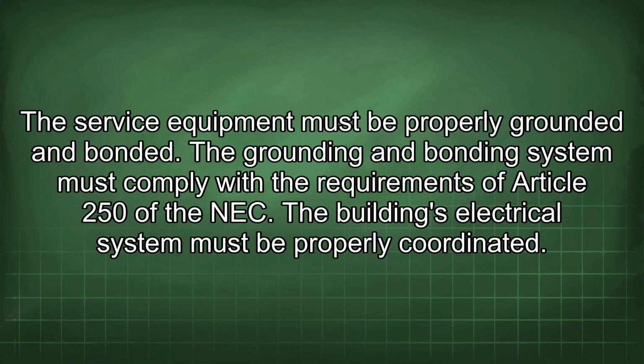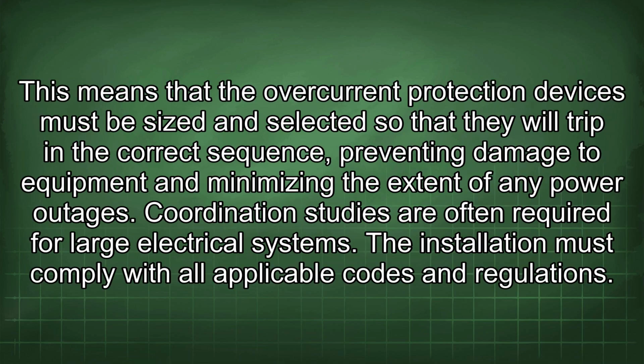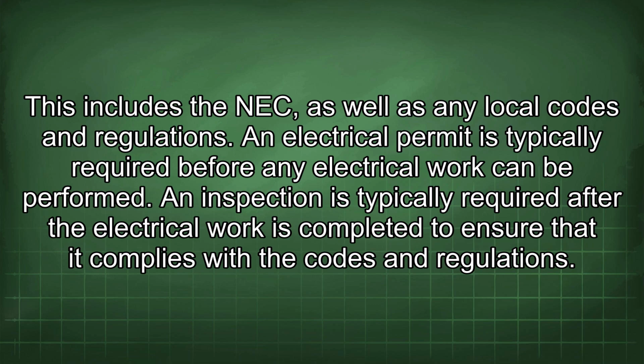The building's electrical system must be properly coordinated. This means that the overcurrent protection devices must be sized and selected so that they will trip in the correct sequence, preventing damage to equipment and minimizing the extent of any power outages. Coordination studies are often required for large electrical systems. The installation must comply with all applicable codes and regulations. This includes the NEC, as well as any local codes and regulations. An electrical permit is typically required before any electrical work can be performed. An inspection is typically required after the electrical work is completed to ensure that it complies with the codes and regulations.